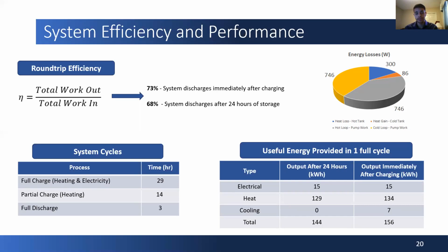In terms of system cycles, a fully charged system requires 29 hours of charging. However, the system can start to provide heat to the home after just 14 hours. Furthermore, the total discharge time for the system is 3 hours. The system always produces 15 kilowatt hours of electricity. However, a total of 129 to 134 kilowatt hours of heat can be provided depending on the discharge time of the system. Also, up to 7 kilowatt hours of cooling can be provided if the system was to discharge right after charging.